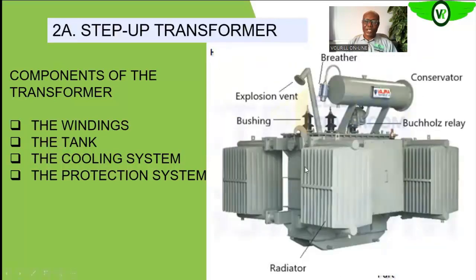So here are some of the components of the transformer that help us to protect the transformer. We know we have oil within the transformer, and because of the thermal expansivity of oil, as it is being heated, it has that tendency of expanding. Once your transformer tank is filled with oil, as it is working, heat is generated. Apart from that, changes in the weather condition of the day can also affect the temperature of the oil. So once it is heated, naturally the oil will expand.